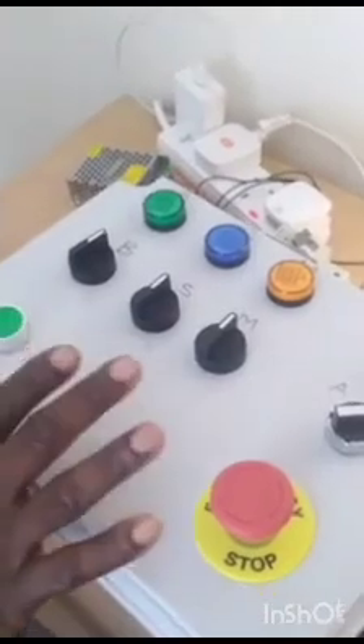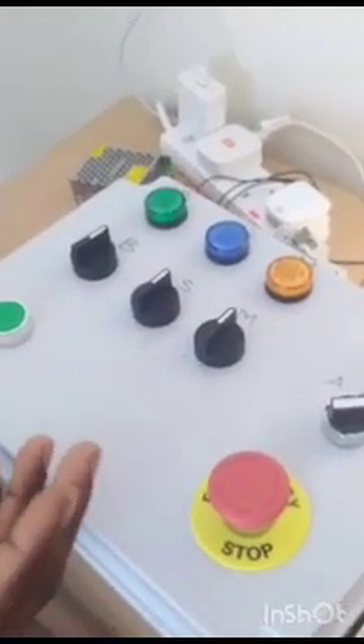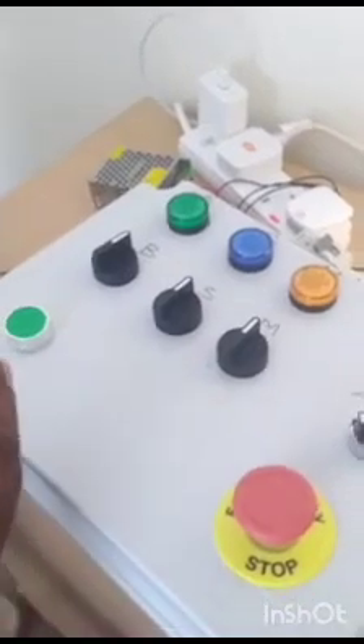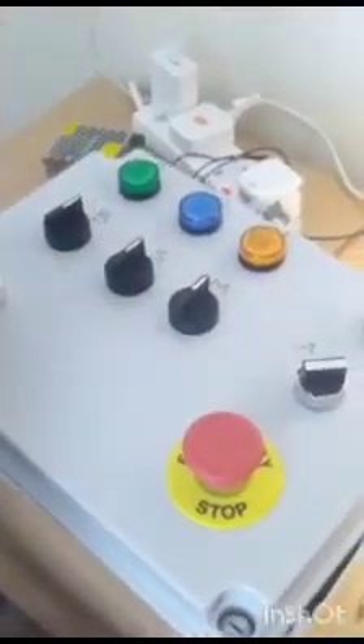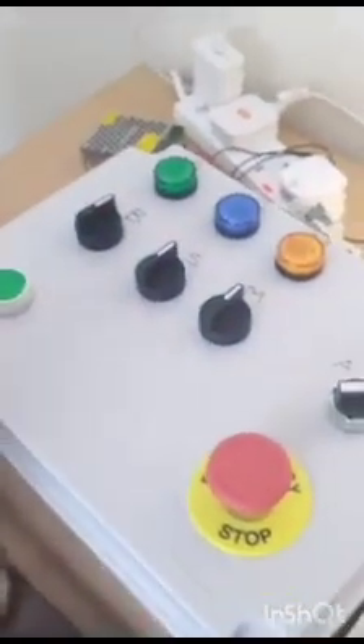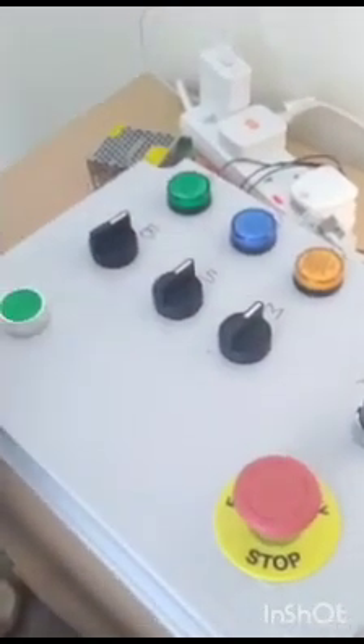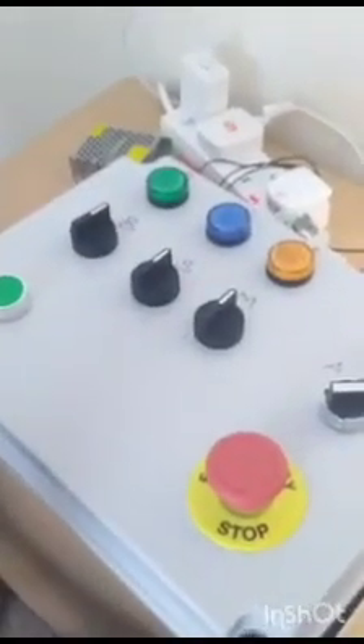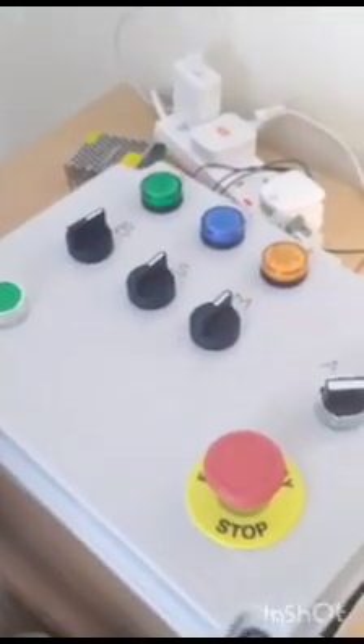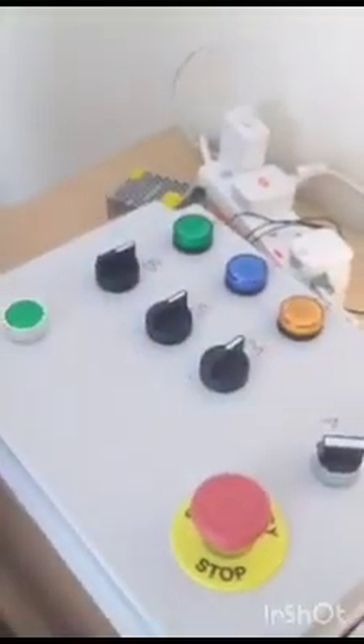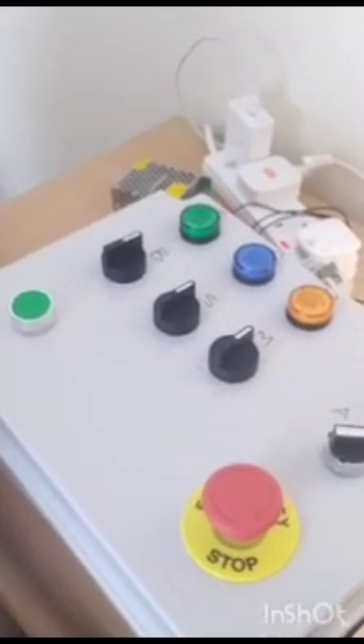I've decided to convert this project to PLC, programmable logic control, and also incorporate HMI, human machine interface, into it, so that if the operator wants to carry out any changes, any adjustment, any settings, they just have to use the screen instead of going to the relay and adjusting it, because that relay is analog. You just touch it on the screen, and it doesn't require space - it's just a small PLC module. You just have to use a ladder diagram to write the program and incorporate it into the PLC module, and it will be better than using these elaborate components.